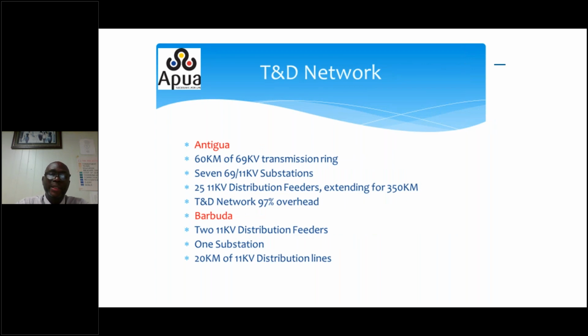The T&D network, just quickly: in Antigua, we have a 69 kV ring system. It's small, but very complex, and I think Roland mentioned that before, that even though we're very small, it's very complex. You have 7 substations and quite a bit of distribution feeders. In Barbuda, very small, only two distribution feeders and 1 substation. The substation is effectively the power station. And most of the system is overhead. In fact, there's a project where we put a great deal of the Barbuda electricity network underground for resiliency measures. Next slide, please.